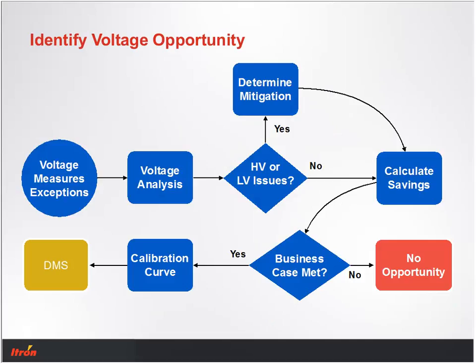We look at the voltage measure exceptions, looking for those high measures and those low measures. The box voltage analysis filters them to highlight the ones that are serious to us. We then determine if they are or are not a problem. If they're out of band, or projected to be out of band, then we have a problem, and we need to do something if we're going to have any opportunity to reduce voltage.